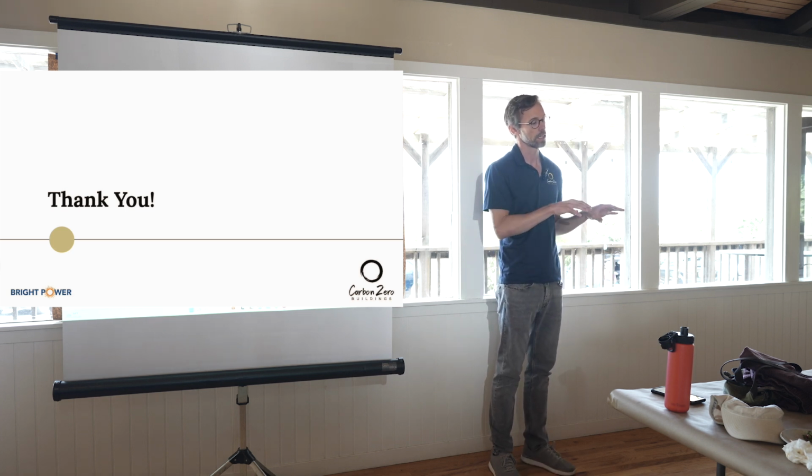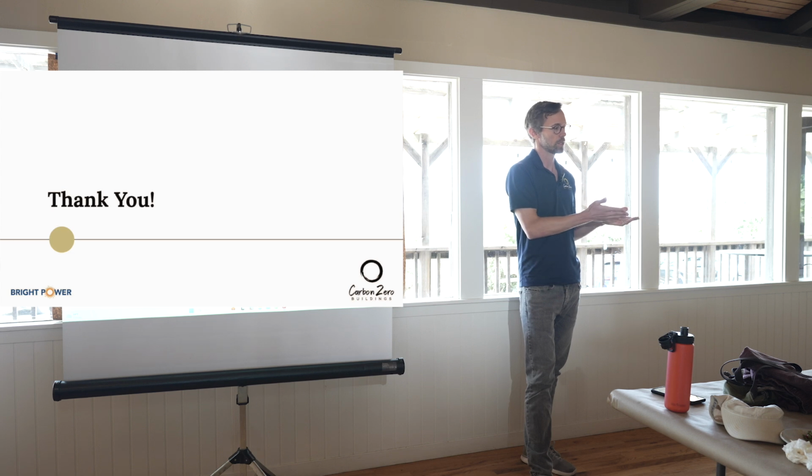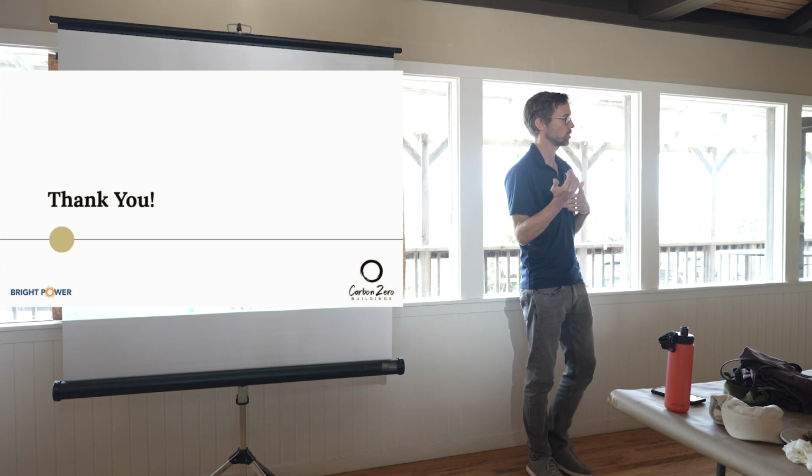But anyway, leaving that aside and coming to your question about SMUD, SMUD definitely helps in terms of the payback side because you actually can get savings from that switch from gas to electric. In this case, with unitary systems, most of those savings are going to the residents, so there's that split where the resident is paying that bill. But SMUD at 13, 15 cents per kilowatt hour versus PG&E at 35 to 40 cents a kilowatt hour with the same gas prices, the paybacks in SMUD, heat pump water heaters actually can generate some dollar savings, which is nice, whereas in PG&E they don't.